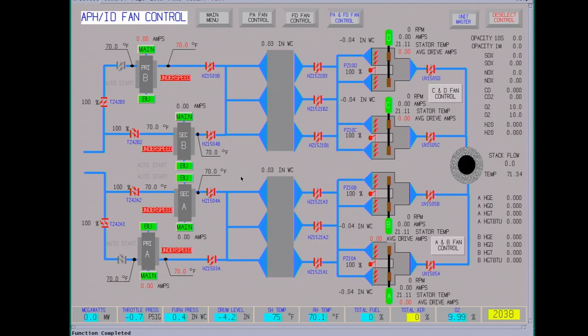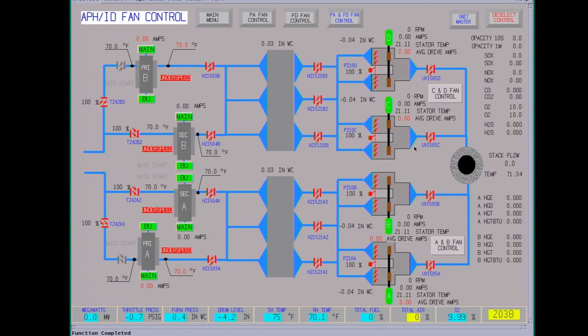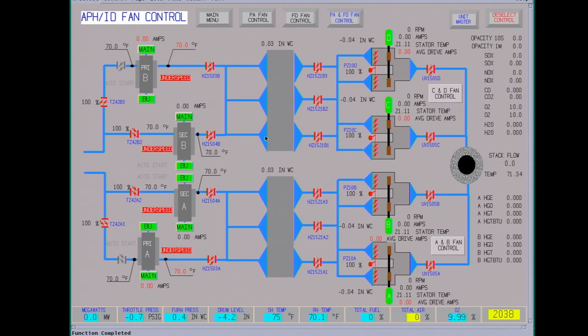Good day, this is a video on starting up a coal plant fans from cold start up to purge. The basic equipment lineup: we have our induced draft fans here, there are 3,500 horsepower motors. From here it goes up to the stack. Upstream we have the precipitator, which takes out all the particulate. Ahead of this we have air preheaters.